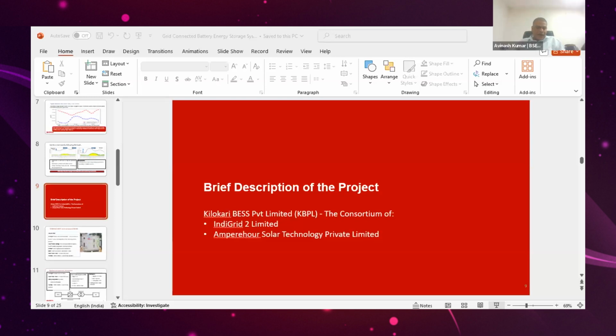BRPL has installed this 20 megawatt, 40 megawatt hour battery energy storage system. The developer is Kilokari BESS Pvt Limited (KBPL), which is joined by the Global Energy Alliance for People and Planet (GEAPP), and this is under the BOOT mode, build, own, operate, and transfer, for 12 years. The system is designed for 12 years and 2 cycle operation per day. The total capacity is 20 megawatt, 40 megawatt hour, meaning 2 hours capacity for 2 cycle operation in a day.